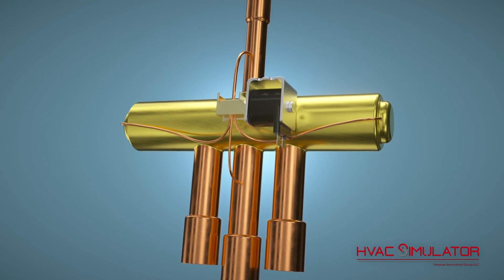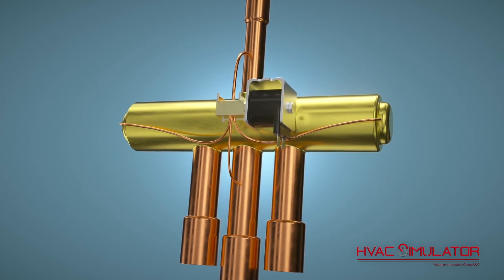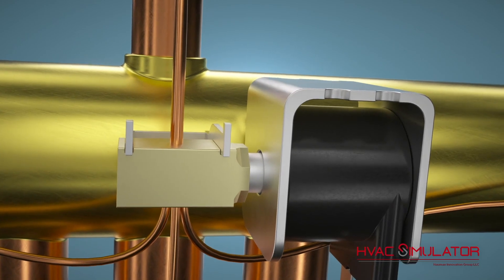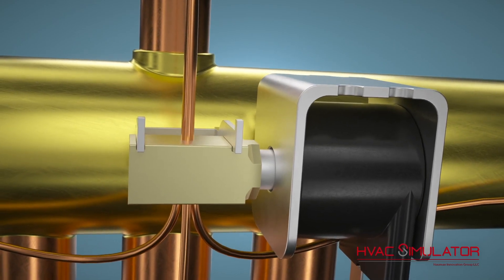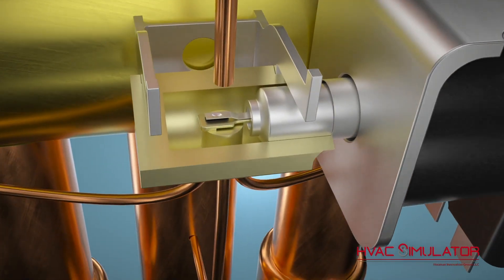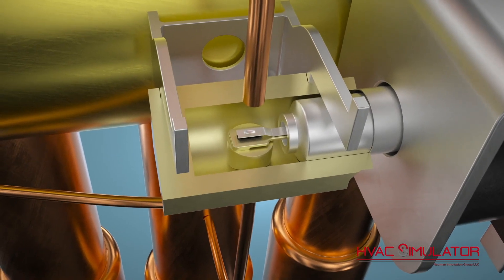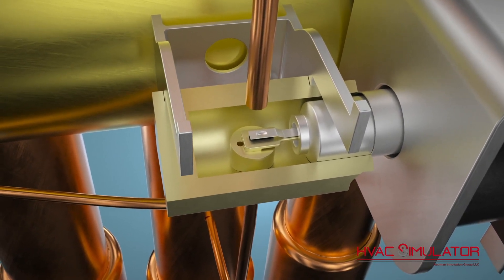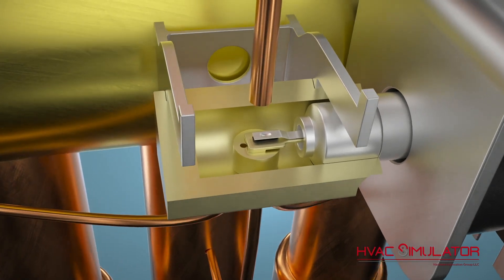When the system switches between heating and cooling, the thermostat sends a signal to energize the solenoid coil and generates a magnetic field. This magnetic field exerts a force on the core causing a mechanical motion. The core and stem move, causing the pressures to change in the two outer capillary tubes.